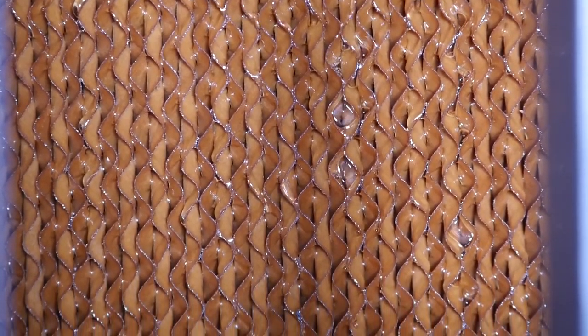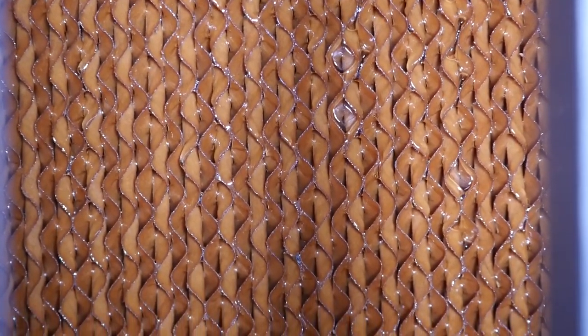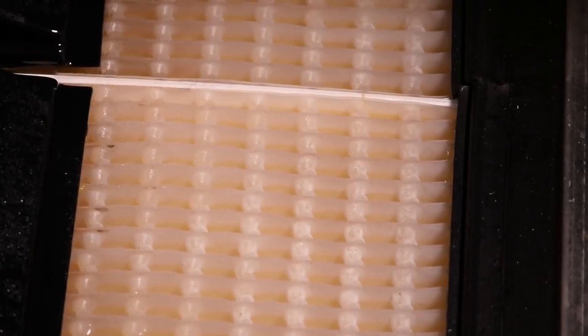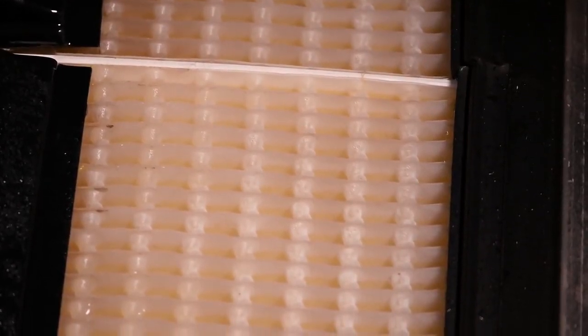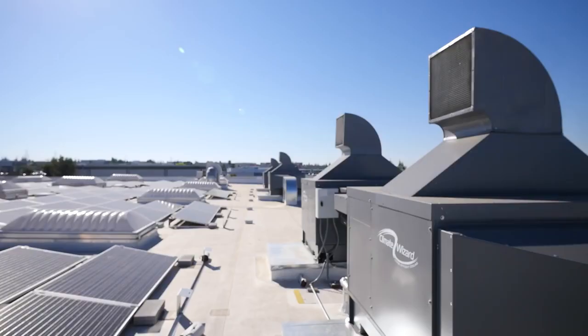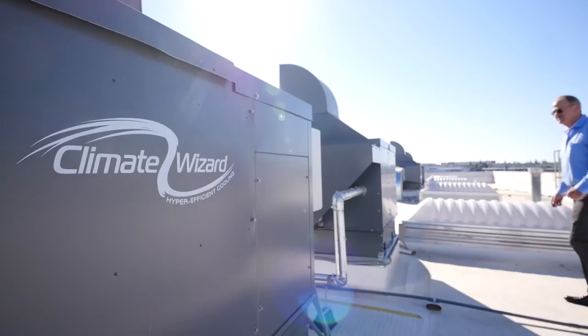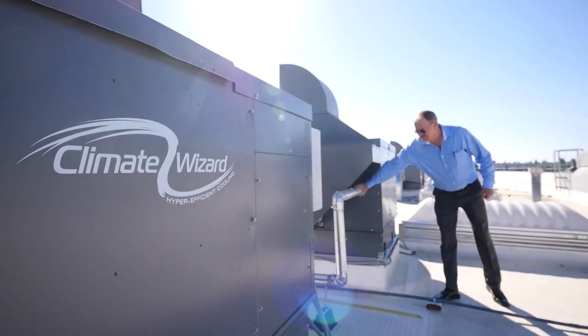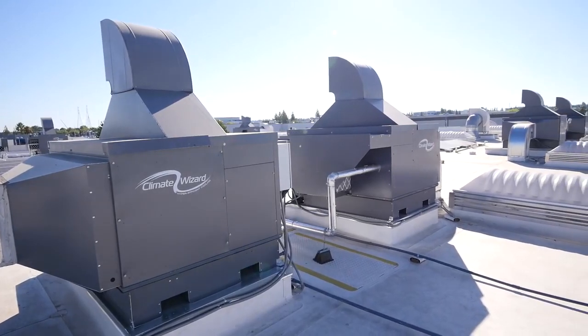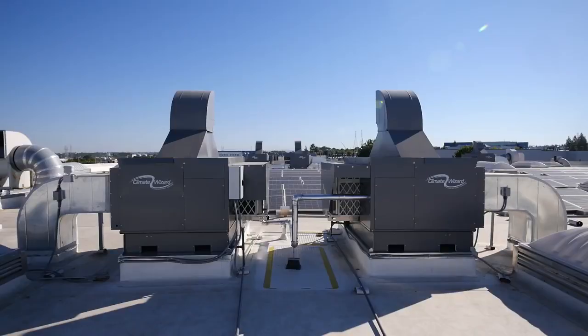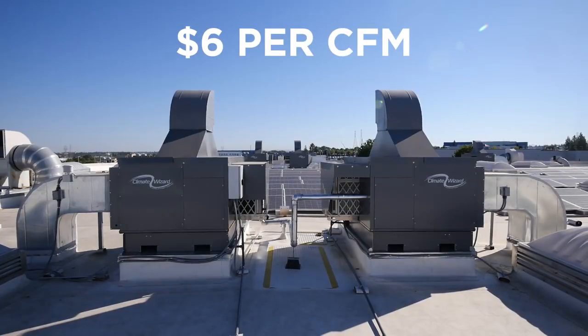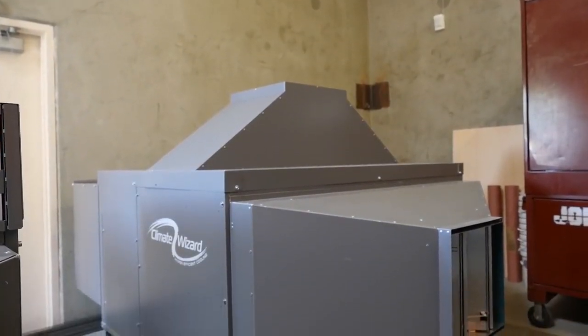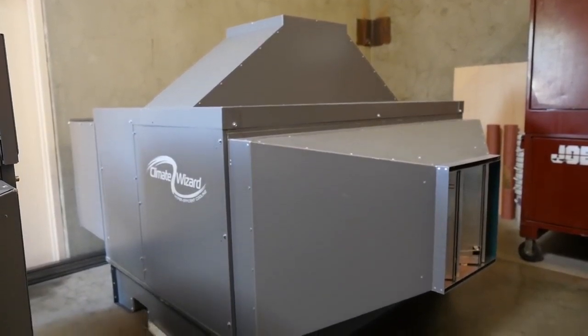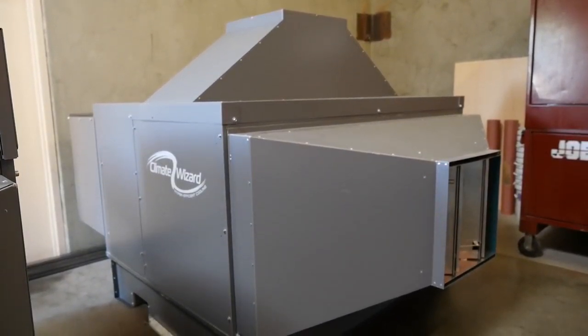Climate Wizard minimizes water use by utilizing water-retaining materials in the wet channels of the heat exchanger. It can work with water supplies of varying quality. The cost of the water used is a small fraction of the money saved from reduced electricity consumption and peak demand. The cost of a Climate Wizard installation varies with the project details, including the number and size of units. The manufacturer estimates that Climate Wizard installations typically cost about $6 per CFM of supply air delivered. Distributors work with potential customers to calculate the expected payback period before an investment is made. Of course, actual payback will vary in each circumstance, based on factors like hours of operation and numbers of units, but many customers who have installed the Climate Wizard report payback in a few years.